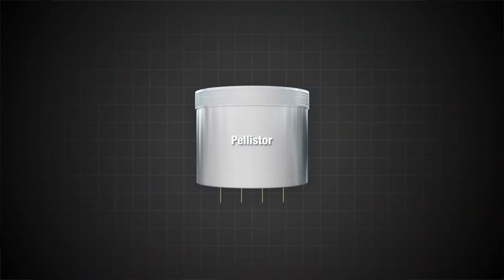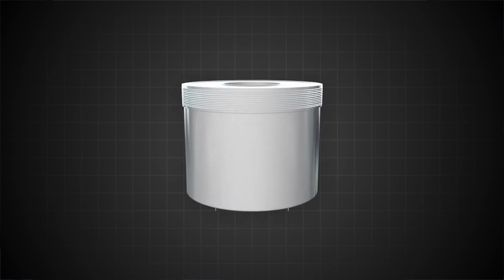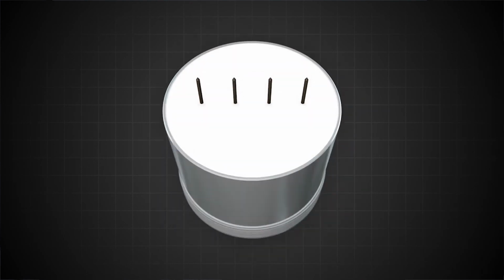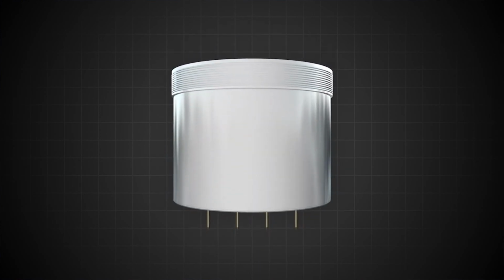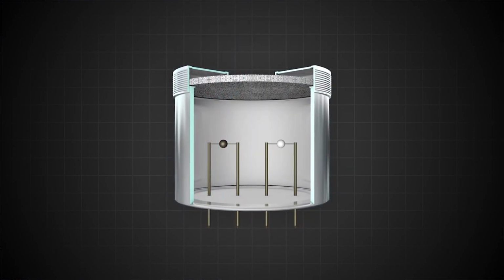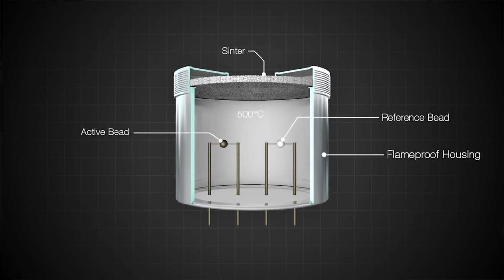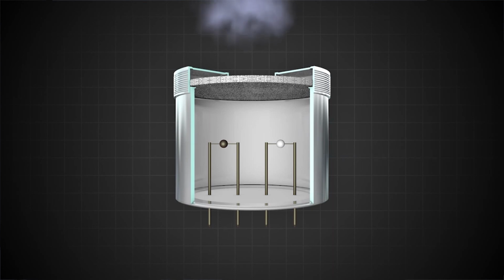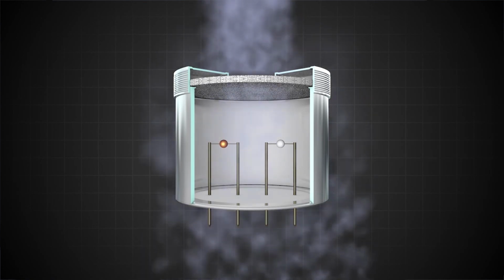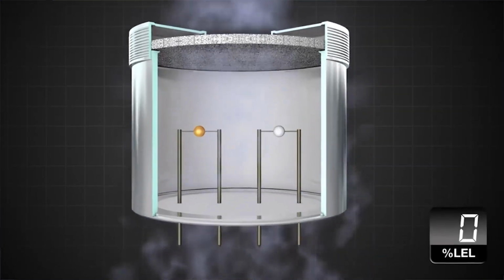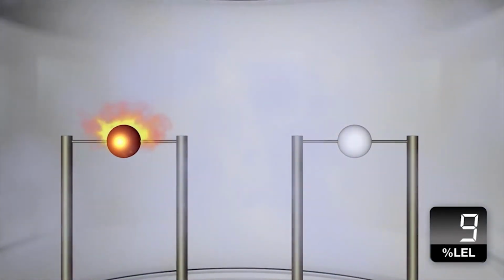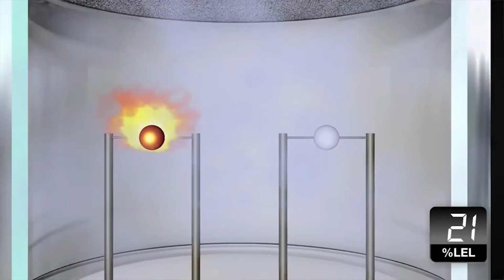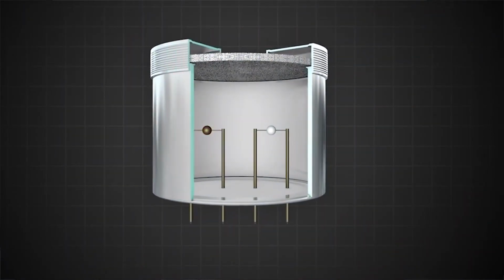So the LEL sensor that I passed around earlier, it's the only sensor that has the full metal body to it. It's got a metal sintered filter on the top of the sensor, and inside the sensor are two catalytic beads. One is the catalytic bead that attracts the flammable gas. The other one is a reference bead. And so as flammable gas starts to enter that sensor, the catalytic bead will actually burn the sample. So your LEL sensor is actually burning the sample, and it compares the heat of the catalytic bead to the reference bead, and that's how the computer in the meter turns it into a number that we can understand. Okay? So remember that your LEL sensor is actually burning the sample.